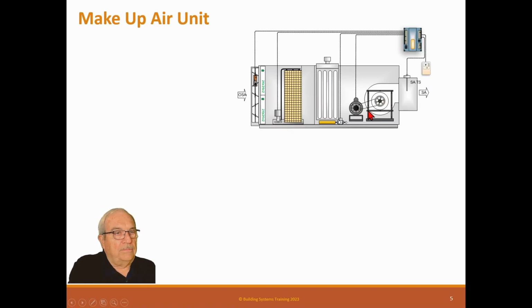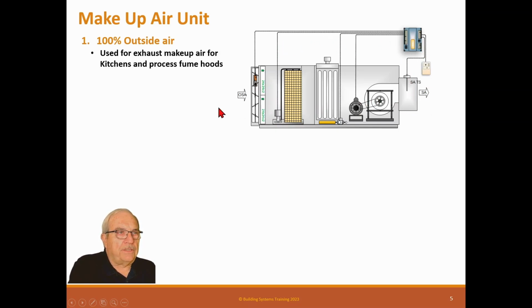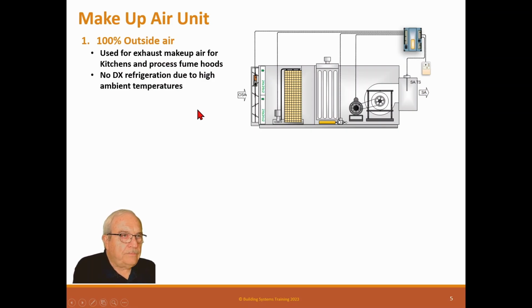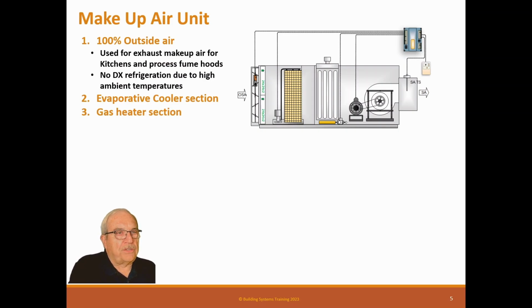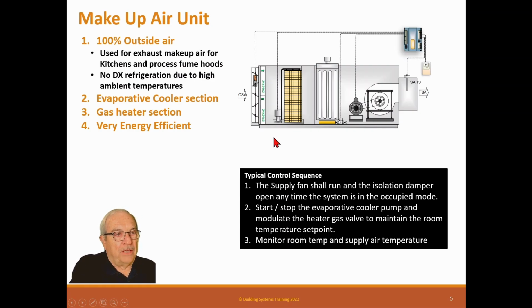So it's got a blower, an isolation damper, filters, an air washer, a gas heater, and a blower to the space, and a DDC system, used for makeup for kitchens and process fume hoods. No DX refrigeration due to high ambient temperatures. Evaporative Cooler section, gas heater section, very energy efficient. Doesn't work very well if you have high humidity. Very efficient on energy, not very good for the space. If you have high humidity, it's not going to provide you much cooling.